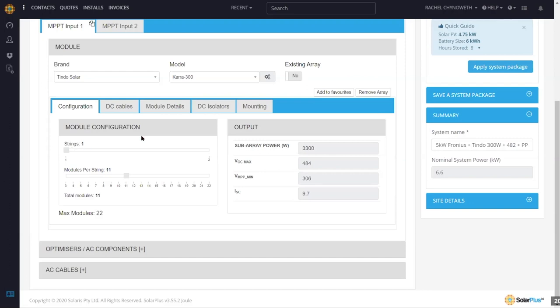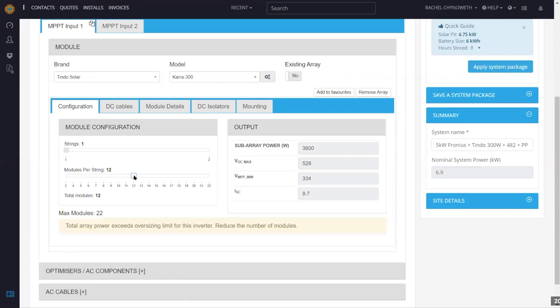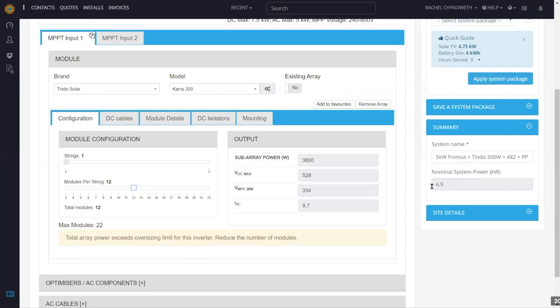I've got two inputs on this inverter and I currently have 11 on one and 11 on the other input. If I change that to 12 panels on this input, our nominal system power was 6.6 kW and it's now 6.9 kilowatts on a five kilowatt inverter. This is just indicating that we're over the 1.33 multiplier — that arbitrary limit to claim STCs on this inverter.